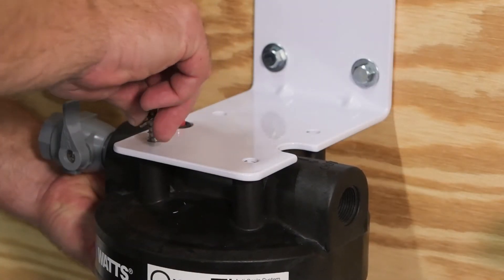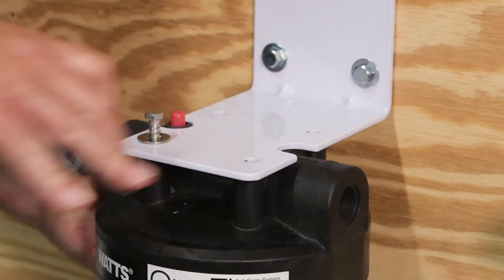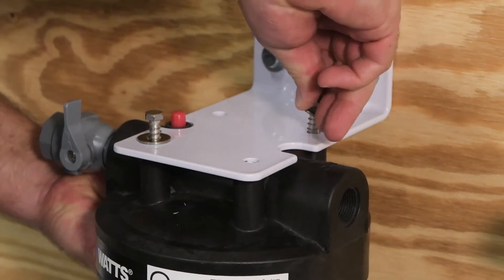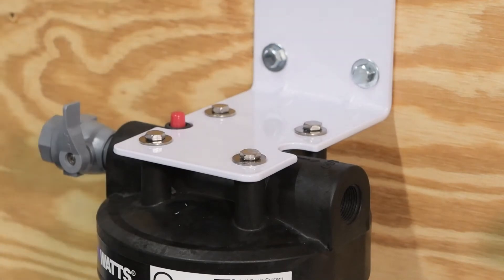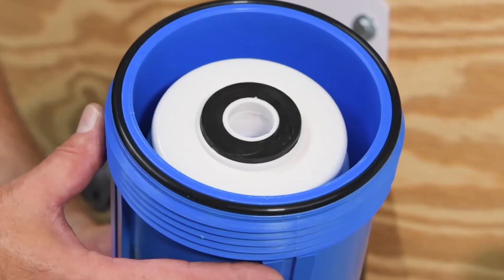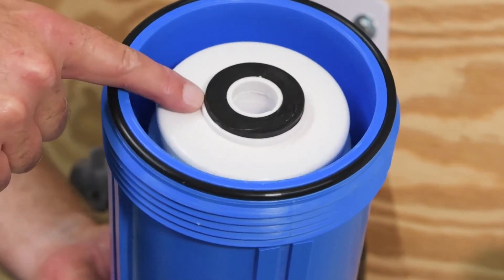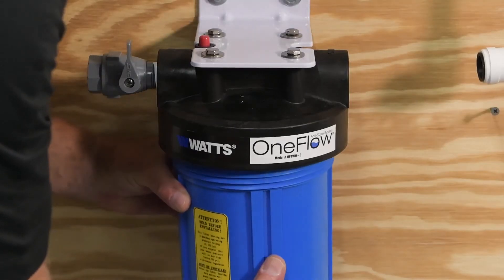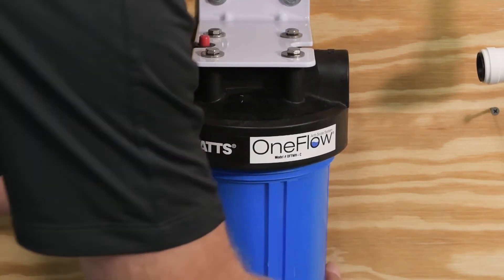Next, you'll connect the head assembly to the mounting bracket. Note the position of the inlet and outlet on the head assembly before connecting it to the mounting bracket. The inlet features a factory pre-installed shutoff. Attach the filter housing — it includes an O-ring and the OneFlow filter cartridge. Ensure both are installed before threading the filter housing onto the head assembly. The housing threads clockwise.